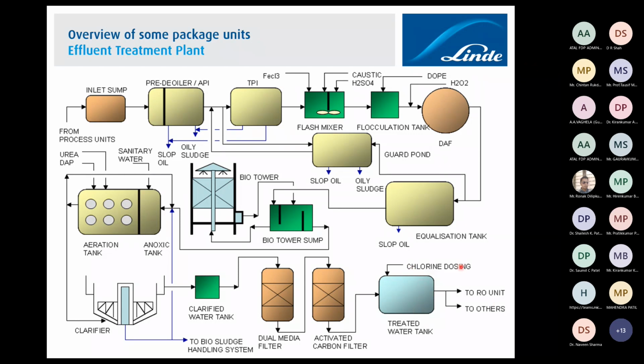And finally, we also add some chlorine. Chlorine is added to disinfect the water, because any residual bacterial or microbial part should not carry over into a subsequent unit. That's why the final killing of bacteria happens, if something is left out, by injecting 0.3 to 0.5 ppm of chlorine. So this is how the entire wastewater treatment unit functions.